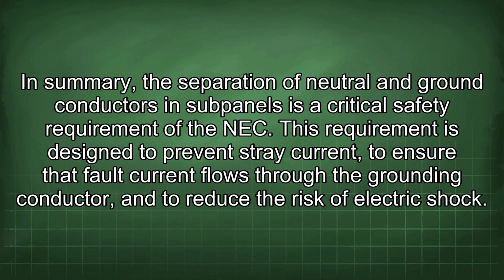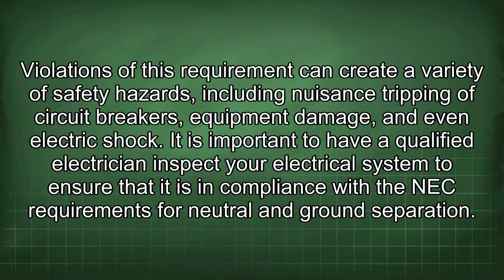In summary, the separation of neutral and ground conductors in subpanels is a critical safety requirement of the NEC. This requirement is designed to prevent stray current, to ensure that fault current flows through the grounding conductor, and to reduce the risk of electric shock. Violations of this requirement can create a variety of safety hazards, including nuisance tripping of circuit breakers, equipment damage, and even electric shock. It is important to have a qualified electrician inspect your electrical system to ensure that it is in compliance with the NEC requirements for neutral and ground separation.